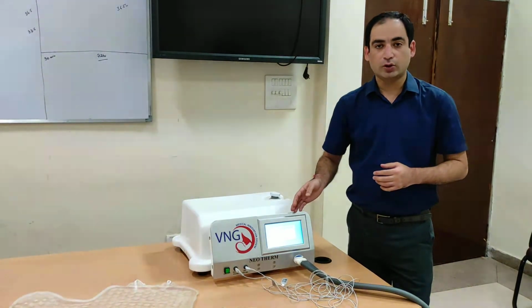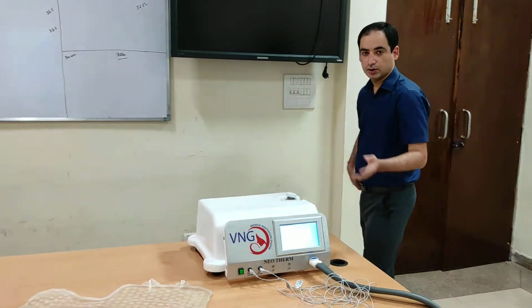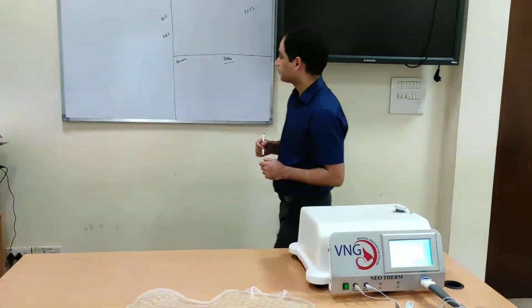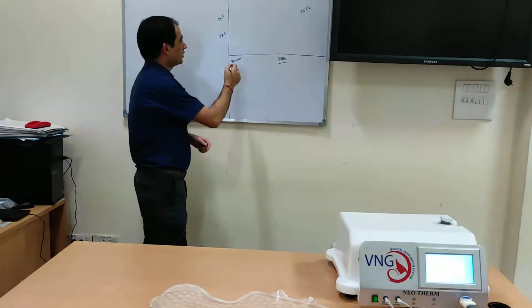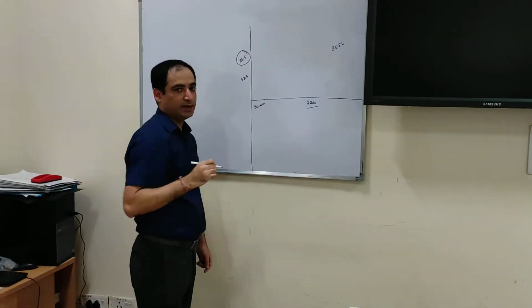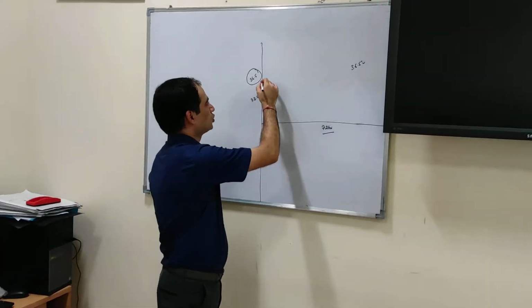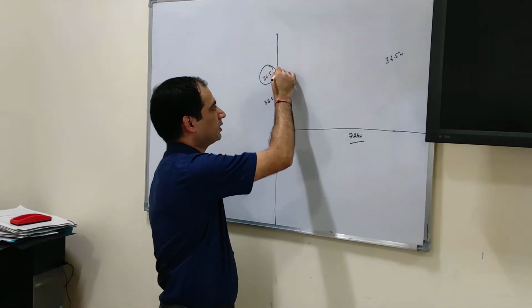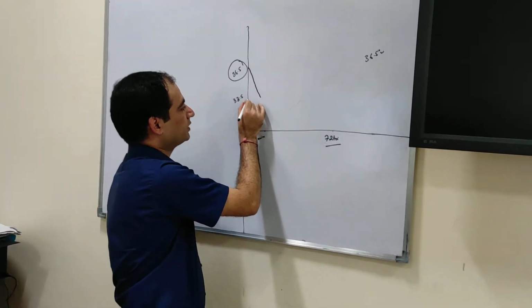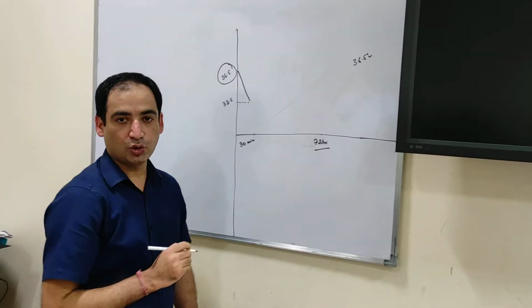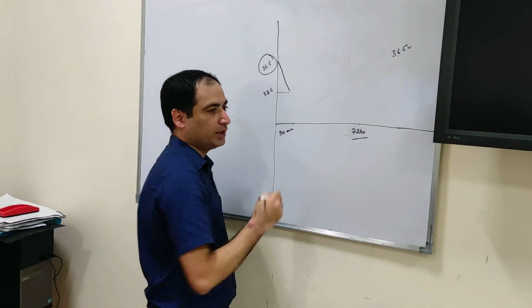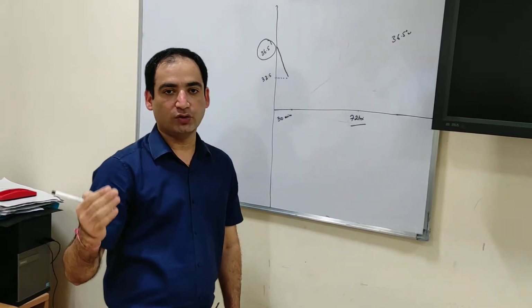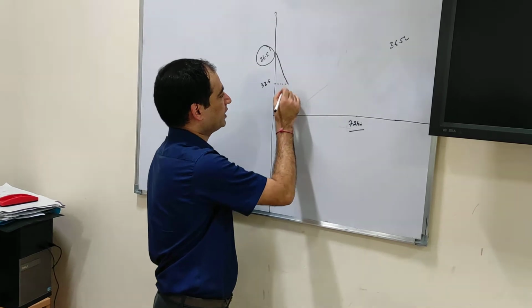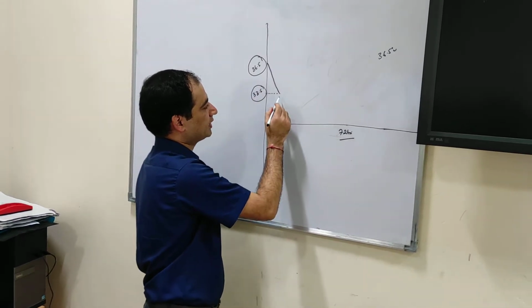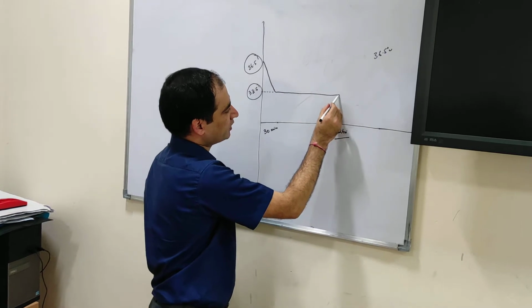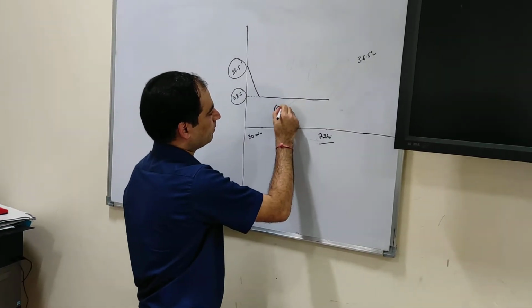Before telling you about the machine, let me tell you about the phases of therapeutic hypothermia. Here in this picture, we have a normal temperature of the baby, that is 36.5 degrees Celsius. Once the baby is started on therapeutic hypothermia, the temperature has to be brought down to 33.5. This is known as the induction phase, and usually induction should be completed within 30 to 45 minutes. Once we have reached this target temperature of 33.5 degrees Celsius, it will continue till 72 hours. This is called the maintenance phase.